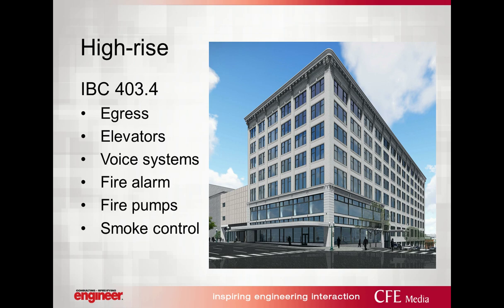IBC Section 403.4 defines systems that are required to be on a standby power source. Now, the primary focus for a building of this type is centered on egress. If elevators are to be placed on emergency power, the designers will need to decide if they will also be used for occupant evacuation by the fire department. Now, we'll discuss specifics on elevators, egress, and smoke control later, but it's those types of systems that result in a high-rise application needing to have emergency power.